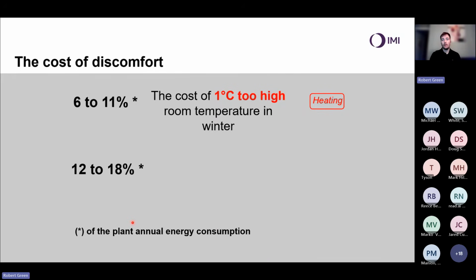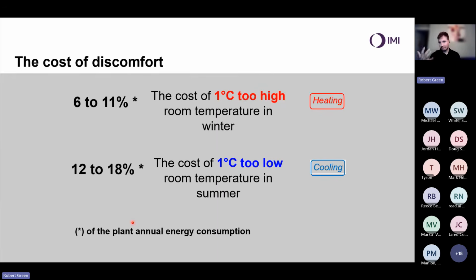It gets even worse with cooling. For 1 degree too low room temperature in the summer, so typically I spend a lot of my time in hotels. Quite often the systems are not very well balanced, and you end up setting your cooling at, say, I don't know, 20 degrees C, when actually a comfort cooling should be around 22 to 24, depending on the building and space you're looking at. And for 1 degree too low room temperature in the summer, we can be looking at 12 to 18%. So we can be looking at some serious numbers in terms of energy consumption, in terms of going for low energy usage from an environmental perspective, but also that's straight on my OPEX. My operational costs of my building are going to increase dramatically for what is effectively only a small change in set point due to a lack of balancing. So that was an overview on why should we balance? Where are these costs associated there?